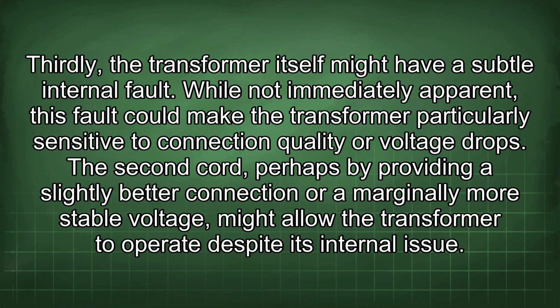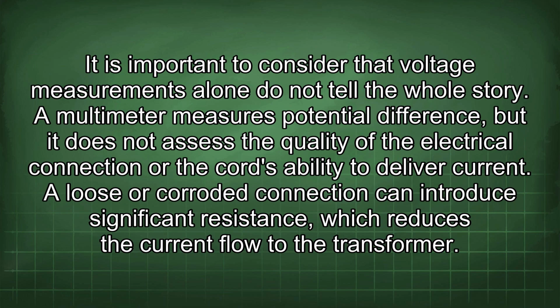While not immediately apparent, this fault could make the transformer particularly sensitive to connection quality or voltage drops. The second cord, perhaps by providing a slightly better connection or a marginally more stable voltage, might allow the transformer to operate despite its internal issue. It is important to consider that voltage measurements alone do not tell the whole story. A multimeter measures potential difference, but it does not assess the quality of the electrical connection or the cord's ability to deliver current. A loose or corroded connection can introduce significant resistance, which reduces the current flow to the transformer.